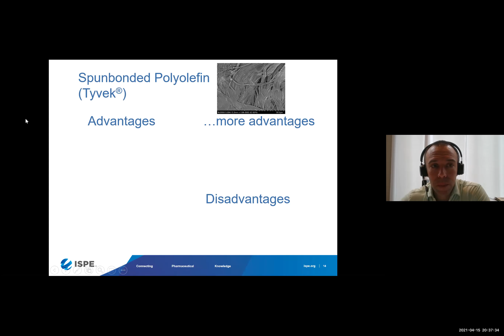Even so, we have better steam penetration and drying properties with the polyolefin material. I have some data later on to show using an ASTM method, the microbial challenge, the difference between the two types of paper and a few different types of polyolefin material. I like to point out here that the polyolefin does not absorb water. It's a hydrophobic material. So during the drying portion of your sterilization cycle, there's not the challenge of trying to dry the sterilization wrapping material itself along with the parts contained within. The hydrophobic nature really allows for fast, easy steam penetration and then fast, easy drying at the end of the cycle.